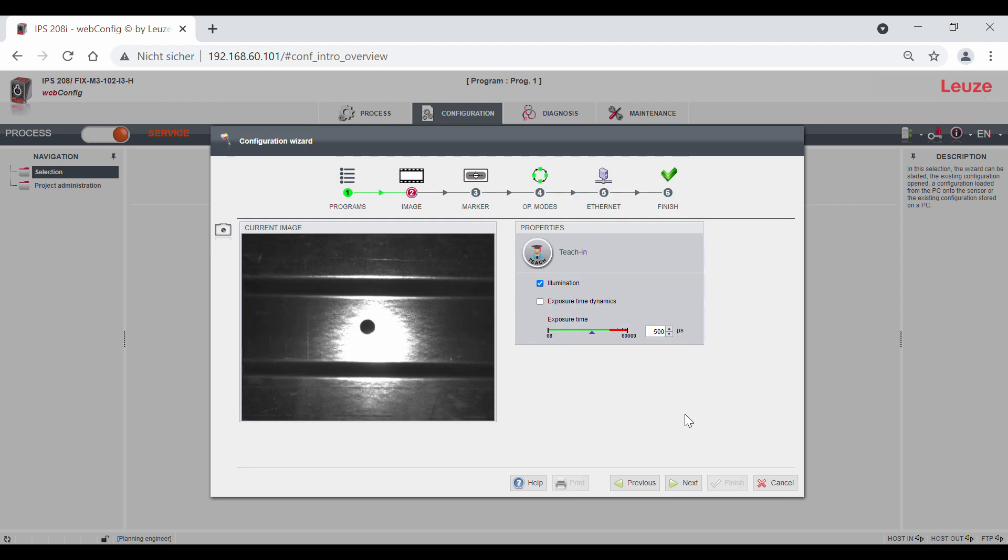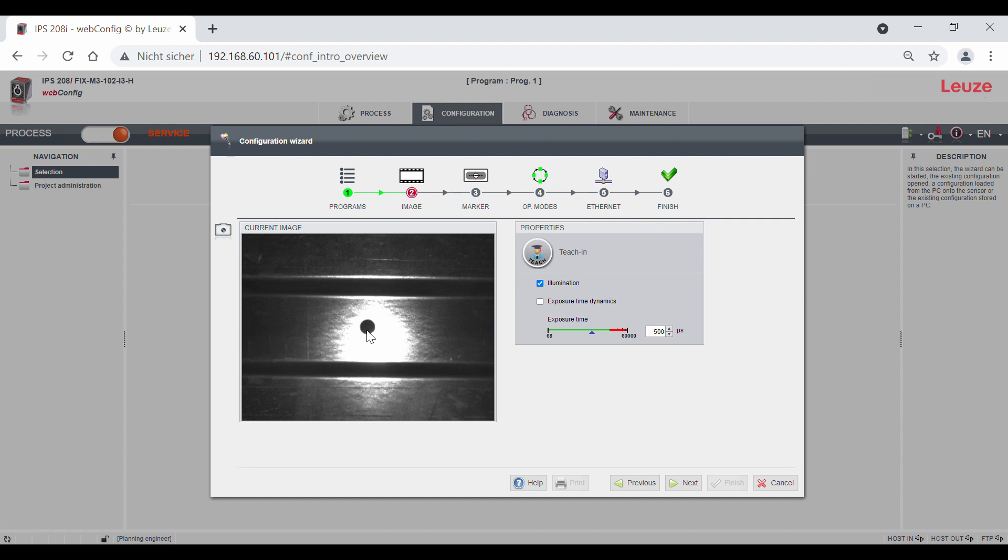The picture tab is about a sufficiently bright contrast of the marker. It is important to get a good, even contrast from the bolt to the hole. Make sure that the sensor is aligned so that the hole is in the center of the image and there are no disturbing reflections behind the hole. Adjust the sensor if this is not the case.